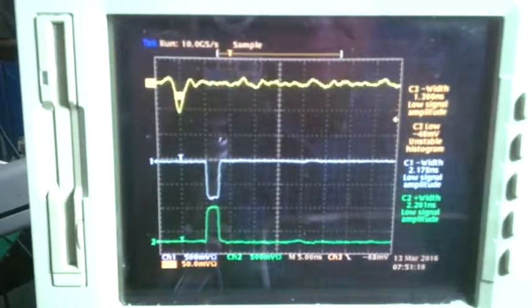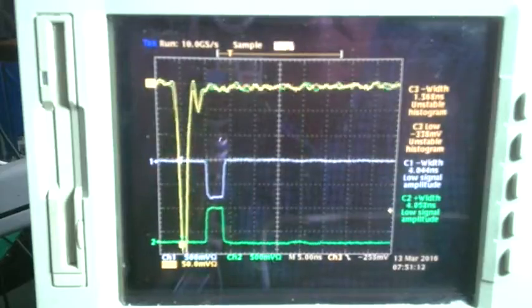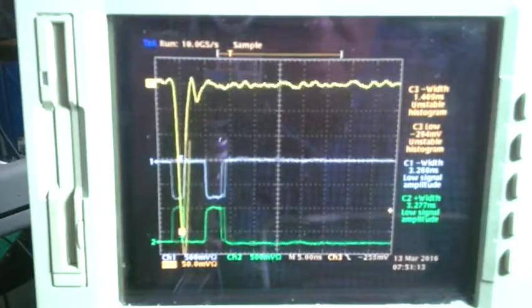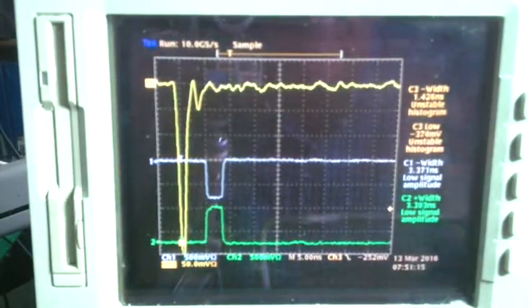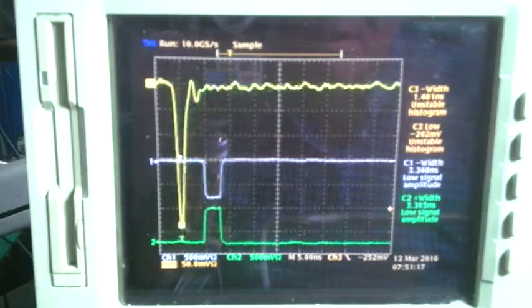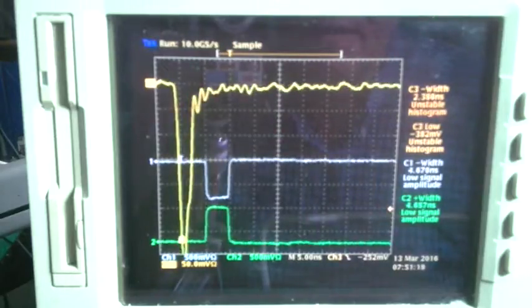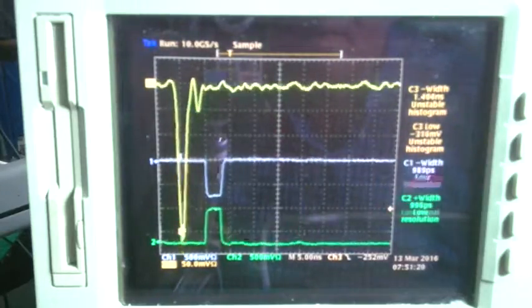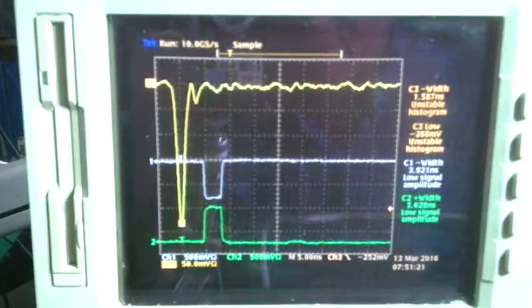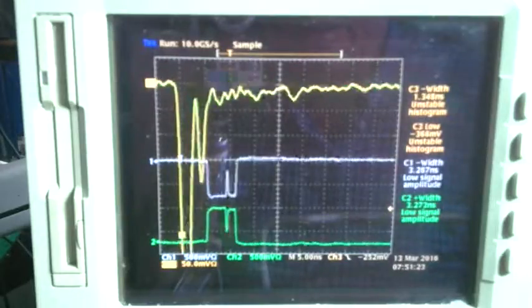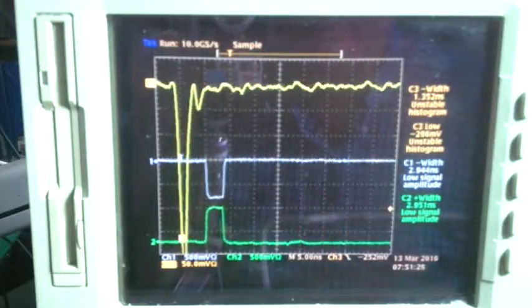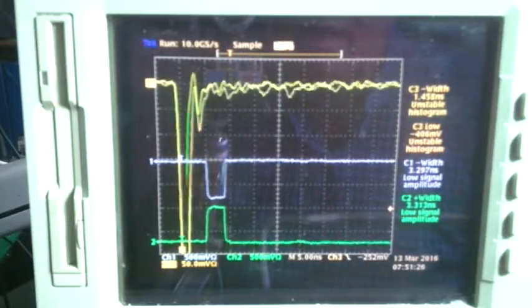If we go down to 200 and roughly minus 250 millivolts, you still see occasional pulses. And one can observe the little glitch on the output of the amplifier discriminator which is caused by ringing in the photomultiplier tube.